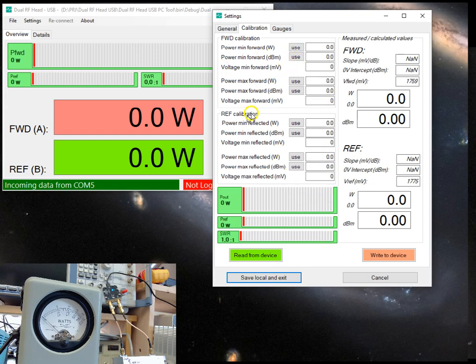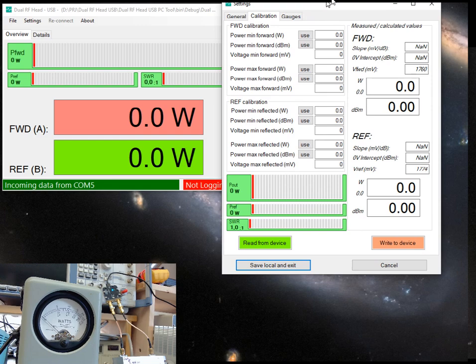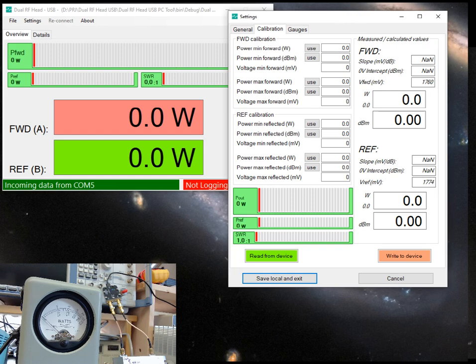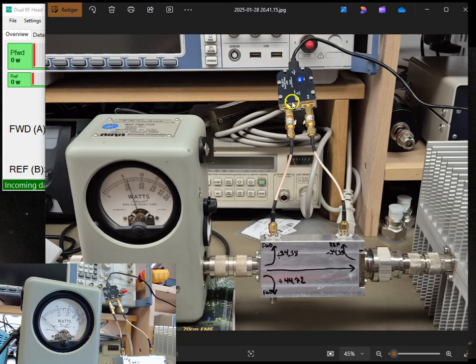Below the two forward and reflected groups, you just have the same meters as you have on the front page: the forward, the reflected and the SWR. You can read the current parameters from the device, and you can write the parameters on this page to the device. This is all that is to the calibration. To give you an idea of how my setup is working, you see on the lower left side here a video running. That's a webcam showing a Bird wattmeter and a dual RF head connected. And I will show you a picture of the same setup.